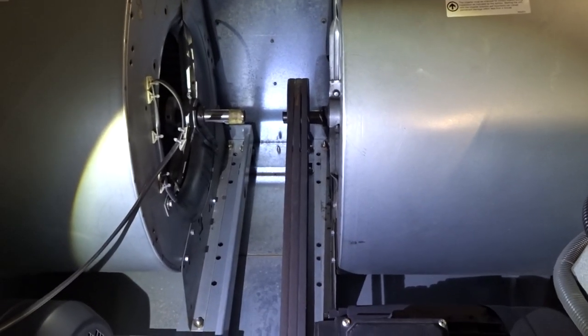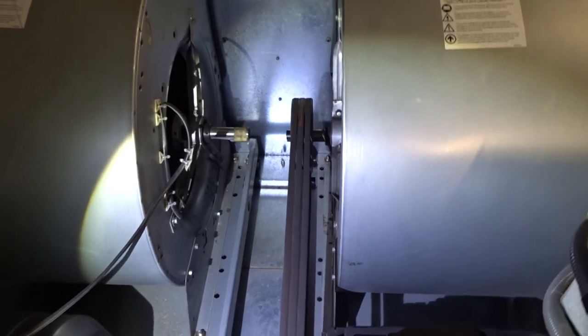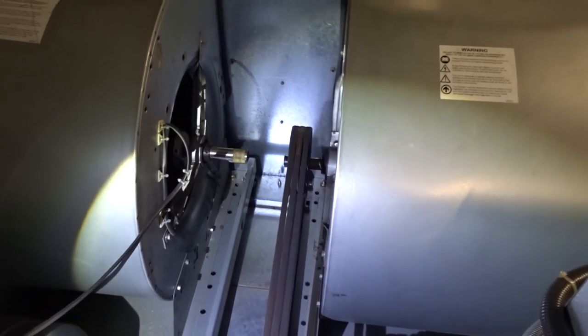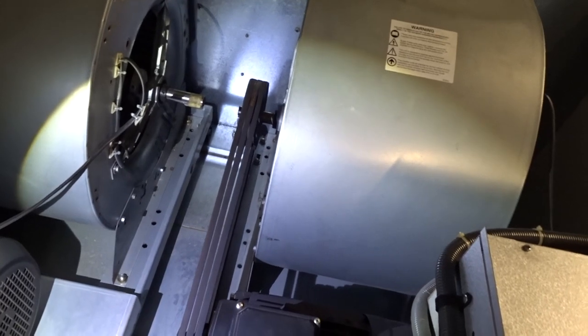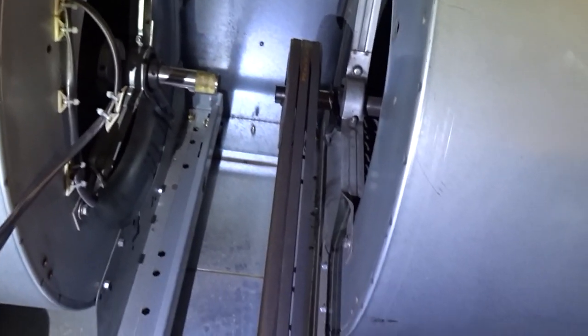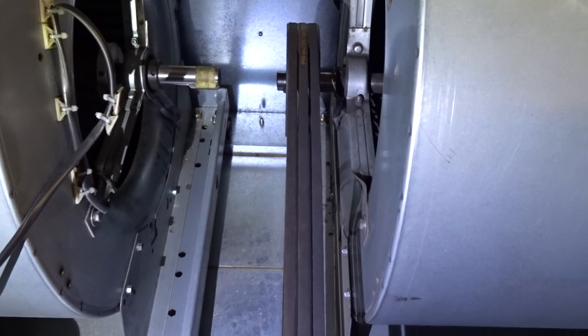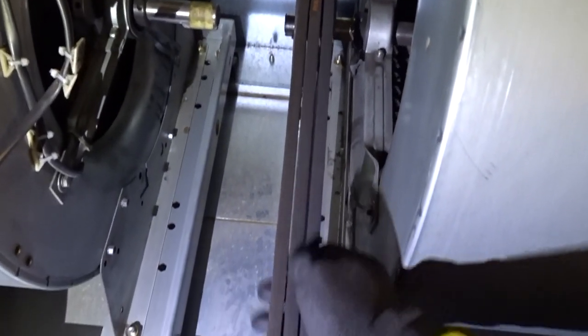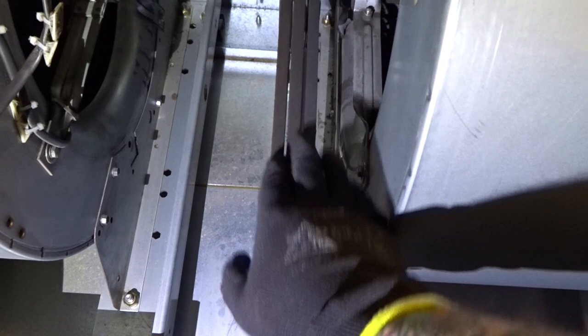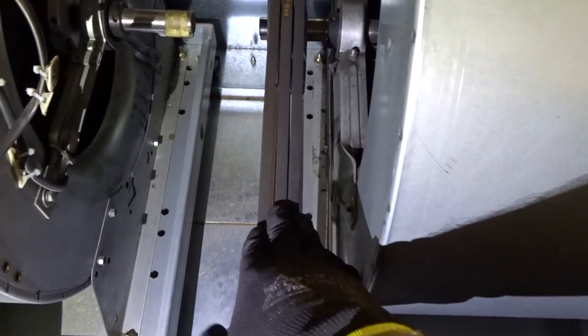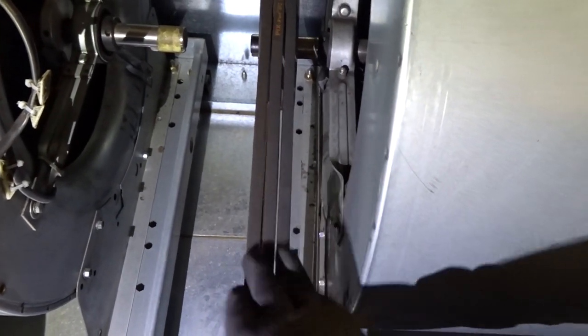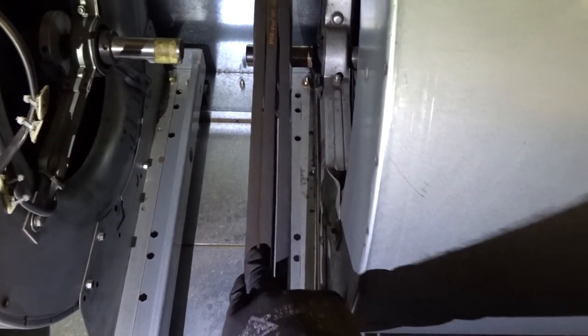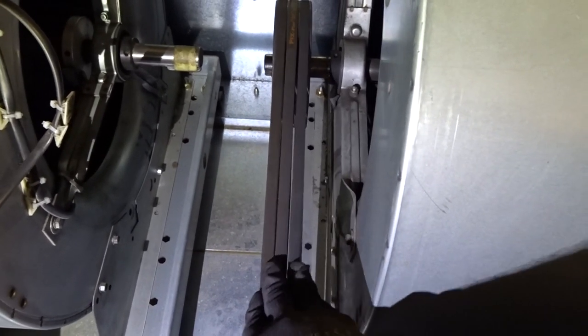Well guys, so far so good. Just put the head torch on now just so I can show you the belts. These fans are fitted with six belts, three belts on each fan and each motor. So all I'm going to do is check the tension of the belts to make sure there's no loose belts.